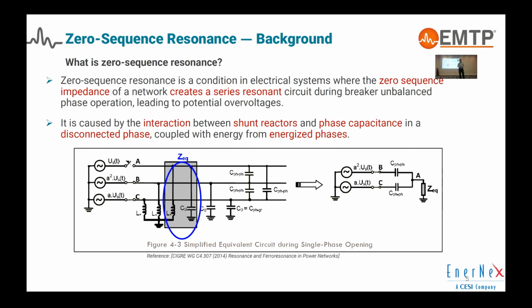Now coming back to the zero sequence resonance background, the first question is, what is zero sequence resonance? It is a condition in an electrical system where the zero sequence impedance of the network creates a series resonance condition during unbalanced breaker operation, along with the source voltage on healthy phases.